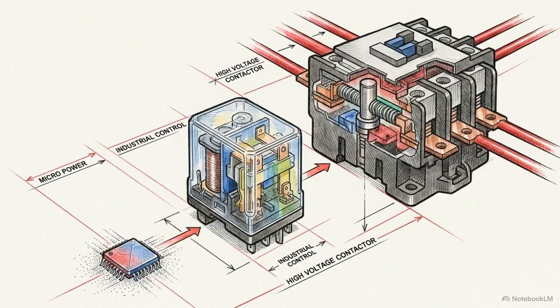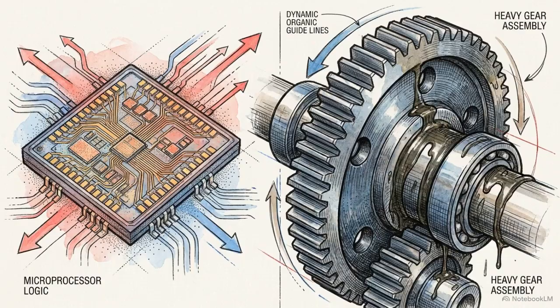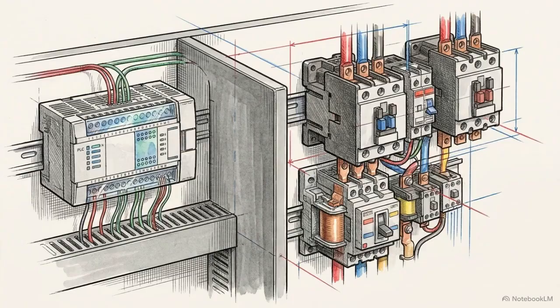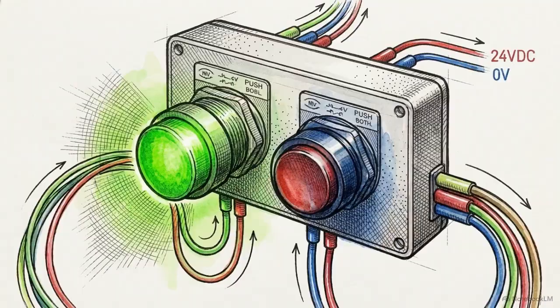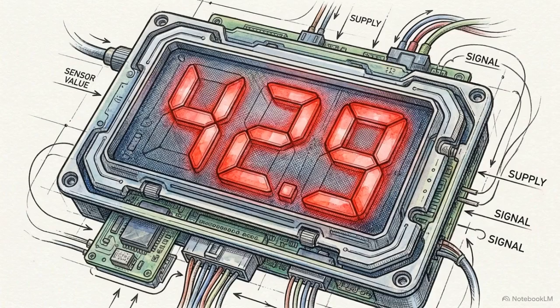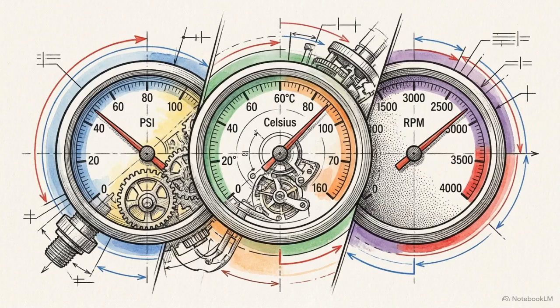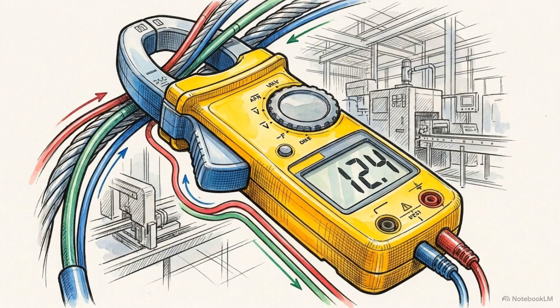The output layer is an escalating ladder of power. It takes a fragile digital 0 or 1 and safely scales it up into hundreds of volts of brute mechanical force, keeping the sensitive controller completely isolated. Binary on-off control handles basic sequencing, but modern manufacturing requires continuous variable data, like fluid pressure, exact temperatures, and specific motor RPMs. To capture variables, we use the 4 to 20 milliamp analog standard.